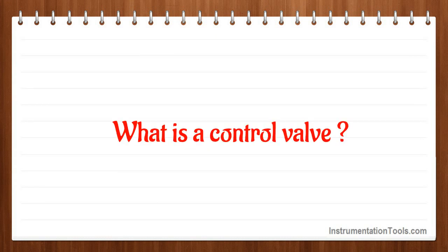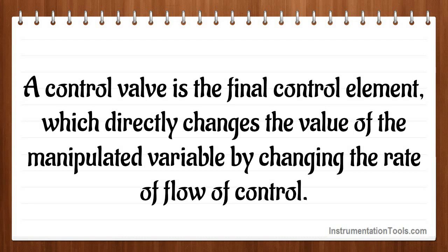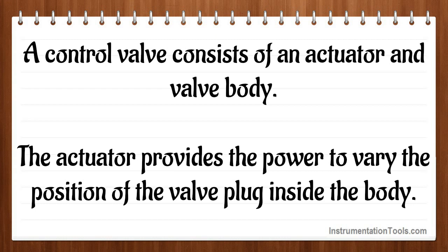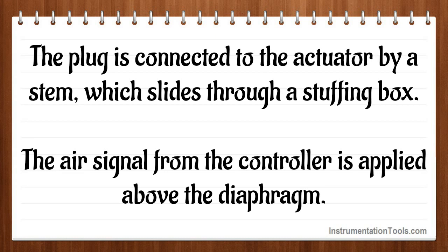What is a control valve? A control valve is the final control element, which directly changes the value of the manipulated variable by changing the rate of flow of control. A control valve consists of an actuator and valve body. The actuator provides the power to vary the position of the valve plug inside the body. The plug is connected to the actuator by a stem, which slides through a stuffing box.